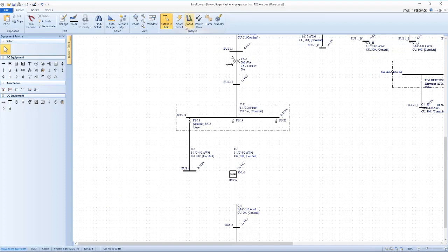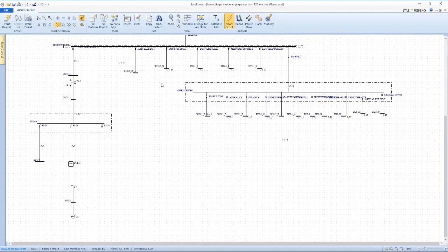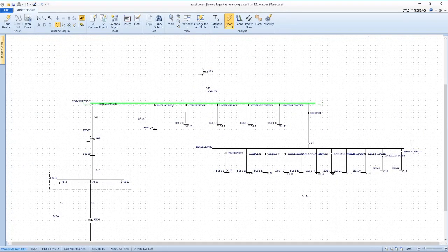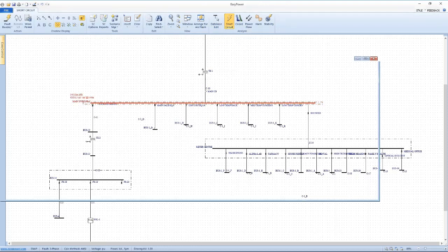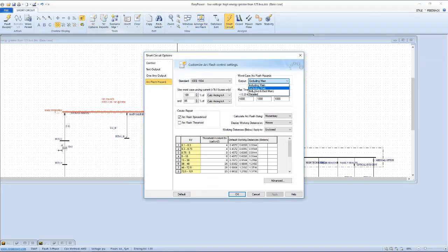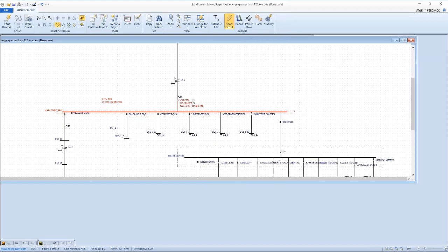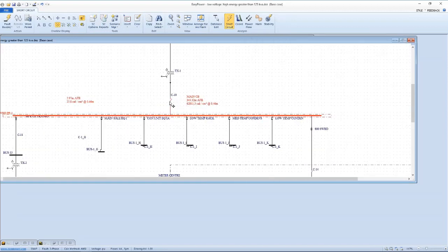What I'm able to do on my short circuit display is show the incident energy on this bus. Let's find a bus that has, here we go. So on this bus, I can fault the bus, calculate incident energy, which is very high, apparently. Maybe it's not even specified. And if I say calculate both excluding and including the main, the tool will show me two different numbers. All right, so based upon whether this breaker is included or excluded, I get two different values of incident energy. Now, that's not what the question was.